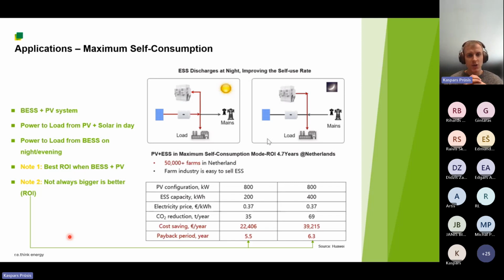So the first of these applications is the one that I think is reasonable for our market, and that's maximum self-consumption, which means that, for example, if we combine this battery energy storage system with a PV system, we can take power generated during the day but not used during that time, and store it in the batteries, and use that energy later when we have energy demand or when the electricity price in the grid is higher, and it's more reasonable for us to use the energy that we have stored.